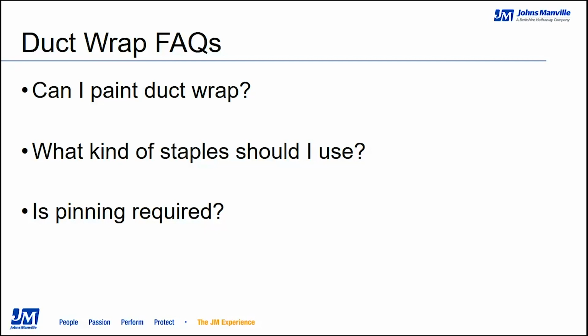And then the last question that we get is about pinning on duct wrap. In that previous picture, you saw that those guys who were installing duct wrap had mechanically fastened that duct wrap on the bottom of that duct side. So, if you're looking at the underside of a duct that spans 24 inches or greater, it's supposed to be secured with a mechanical fastener or speed clips about 18 inches on center. And then you're required to mechanically fasten that facing so it prevents the sag of that insulation with a mechanical pin.